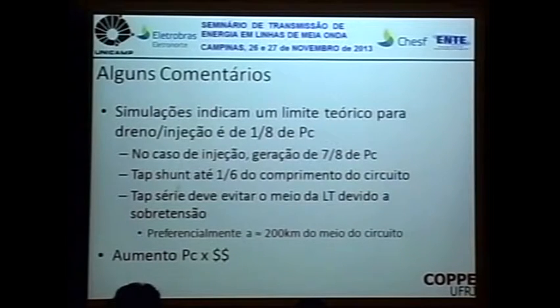Simulations indicated that we have a theoretical limit of around 1/8 of the characteristic power. This is why it's interesting to work with high characteristic powers. On that line of 8 gigawatts, I could drain or inject 1 gigawatt. The only problem is that initially the line needs to open close to the PC. So if I'm injecting 1 gigawatt, my generation cannot load the line beyond one PC. And the connection points have to stay within the characteristic power. The results indicated that the shunt tap can reach up to 1/6 of the length of the circuit, considering this is a half wavelength circuit of 2,500 kilometers. This gives us a certain freedom.